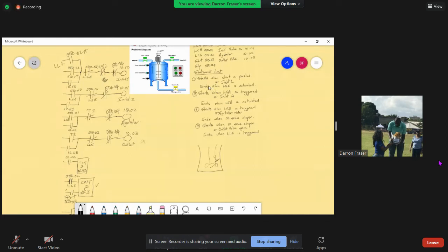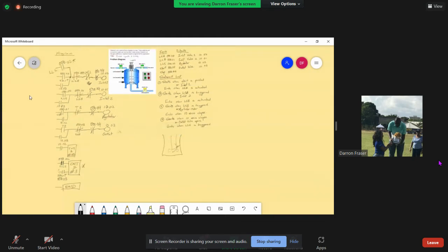What I wanted to introduce today is the counter as a part of the programming and the tools that you have, and to mention how you start over. Now that I'm putting the stop switch, which is 04, I wanted to point out that you could also use a stop switch as the reset for the counter. Because here is the problem: you stop the process and it had gone through two cycles, for example. Then your counter would still be, well, it wouldn't matter because you'd have to start back over the process, you'd have to press the start switch, so it would still clear the counter. But I was just pointing out that on occasion a stop switch is used to clear the counter. So it could be used to clear the counter as well.